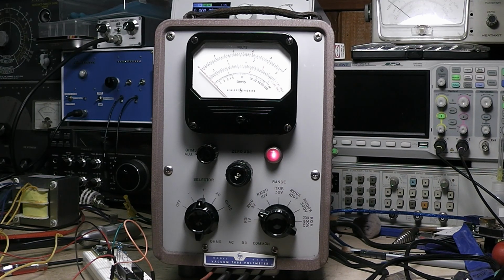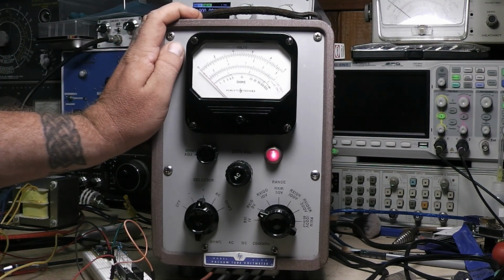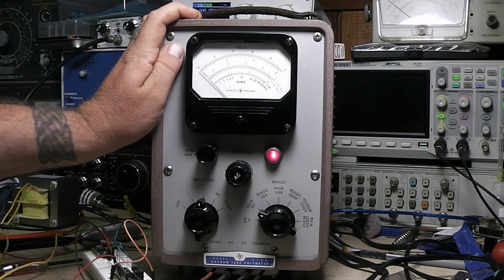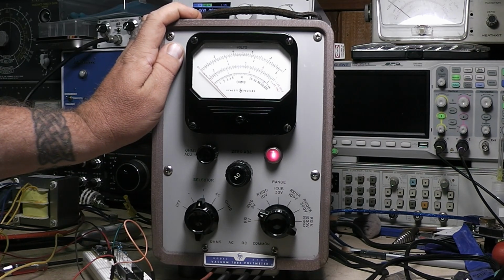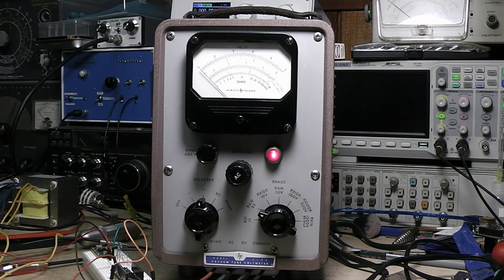And then one thing I want to mention too is, some people do it, your job or something may have access to some fancier test equipment. If you take this to your job and say, well, I work at such and such place and we've got some stuff to calibrate things, one thing you got to remember, they may have power line conditioners and UPS systems and everything. It might be set to run exactly at 120 volts, which is most common nowadays. And then you bring it back home and you plug it in the wall and you're getting 123 volts or 117 volts or whatever, and that's going to affect the accuracy of your calibration.